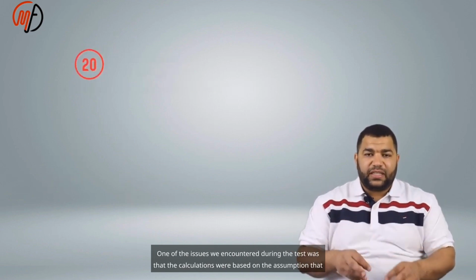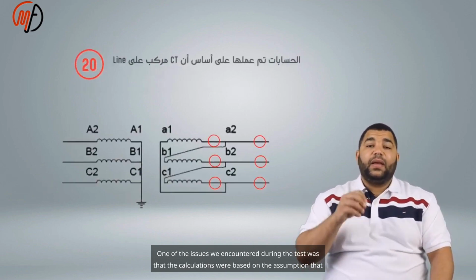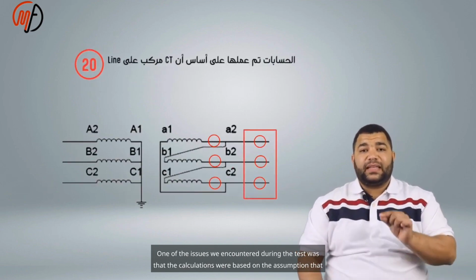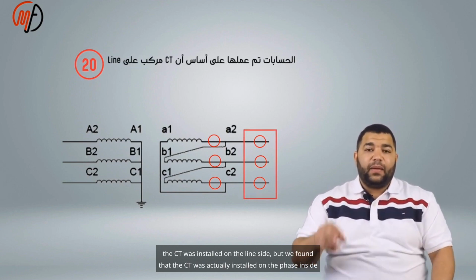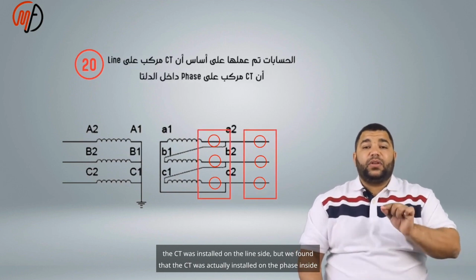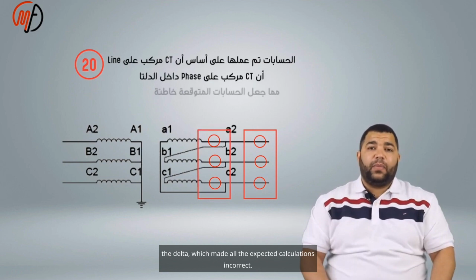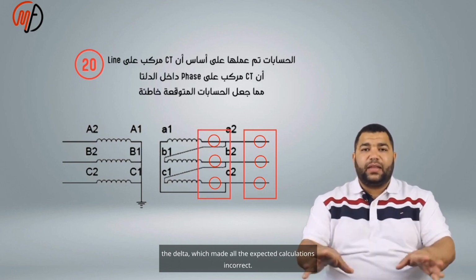One of the issues we encountered during the test was that the calculations were based on the assumption that the CT was installed on the line side, but we found that the CT was actually installed on the phase inside the delta, which made all the expected calculations incorrect.